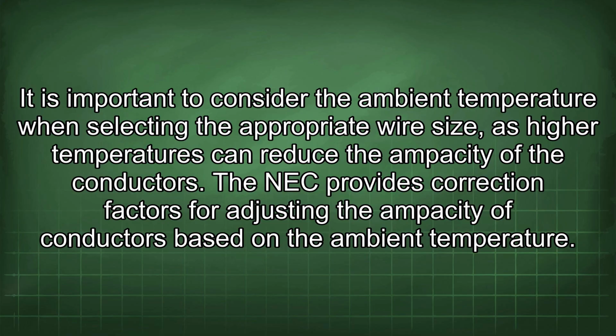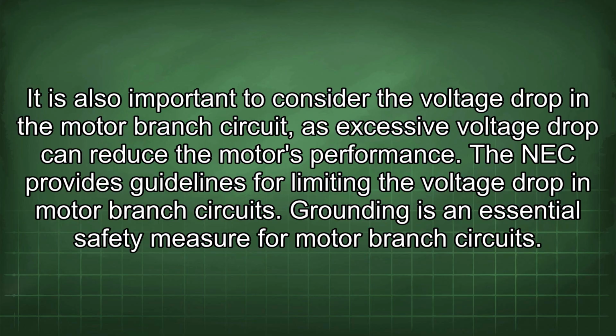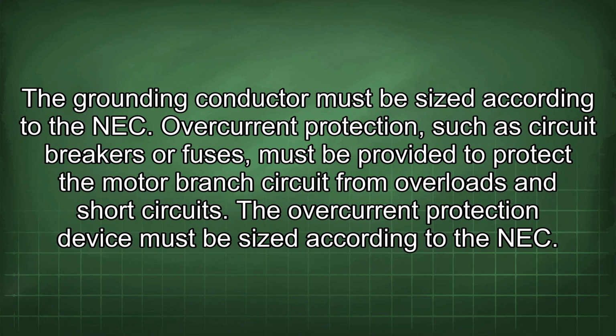The NEC provides correction factors for adjusting the ampacity of conductors based on the ambient temperature. It is also important to consider the voltage drop in the motor branch circuit, as excessive voltage drop can reduce the motor's performance. The NEC provides guidelines for limiting the voltage drop in motor branch circuits. Grounding is an essential safety measure for motor branch circuits. The grounding conductor must be sized according to the NEC. Overcurrent protection, such as circuit breakers or fuses, must be provided to protect the motor branch circuit from overloads and short circuits.